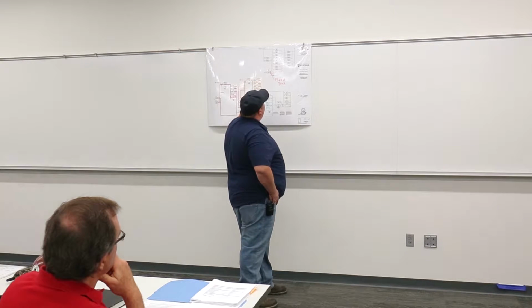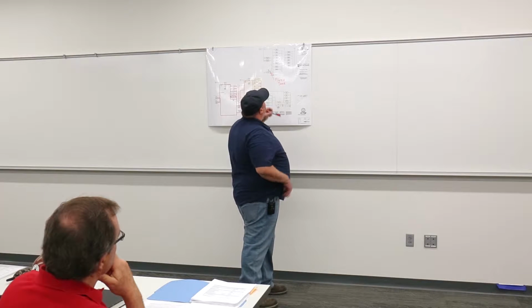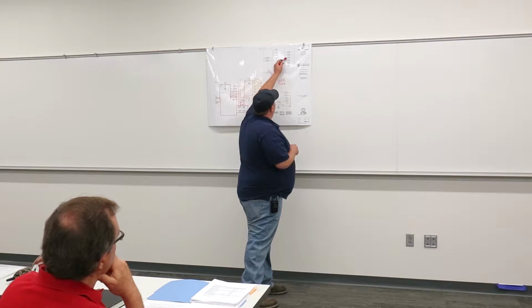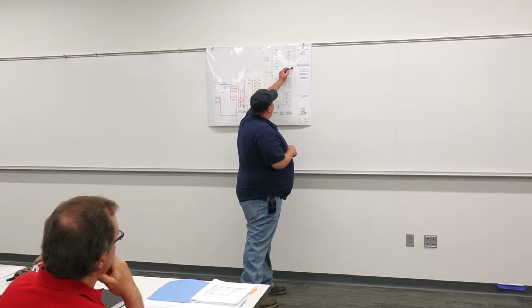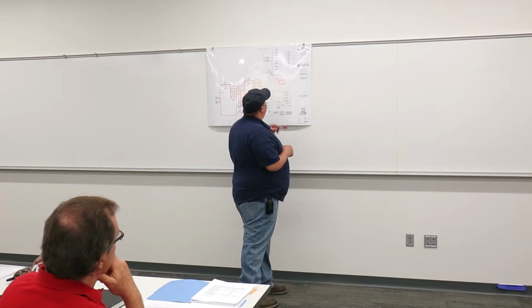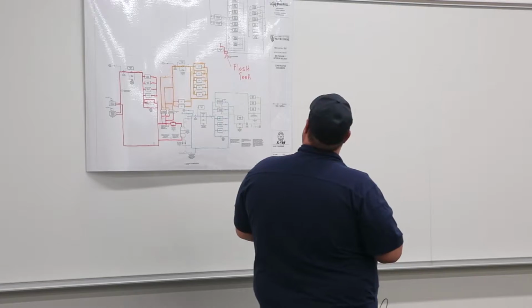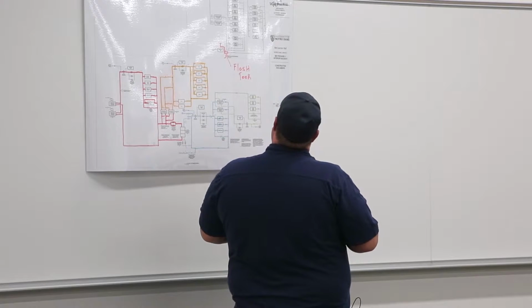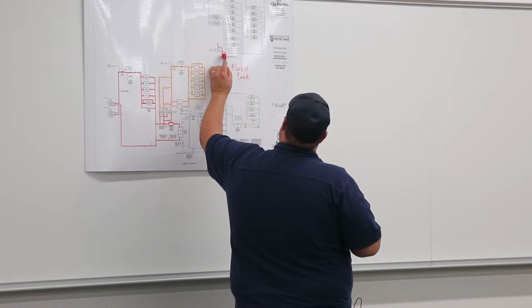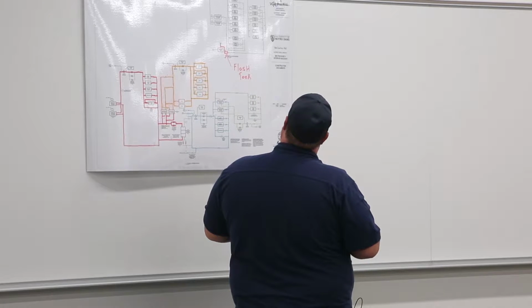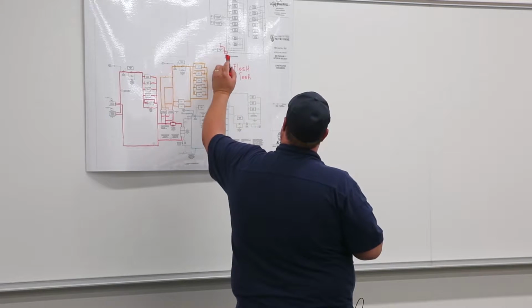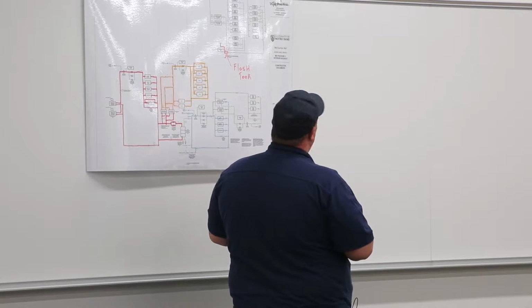In general, the medium pressure steam doesn't feed anything else in the building. It just comes around, feeds our autoclaves. We've got taps on each floor, and it comes around back to the condensate receiver pump and out. By the looks of it, we're flashing off steam into our condensate receiver pumps, so we're in discussion now about adding a flash tank into the system.